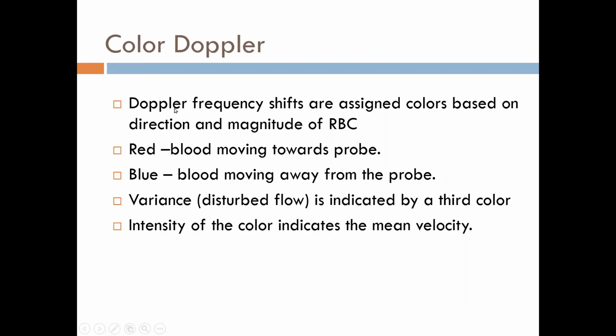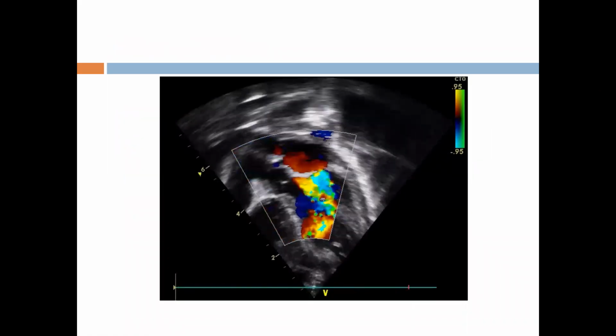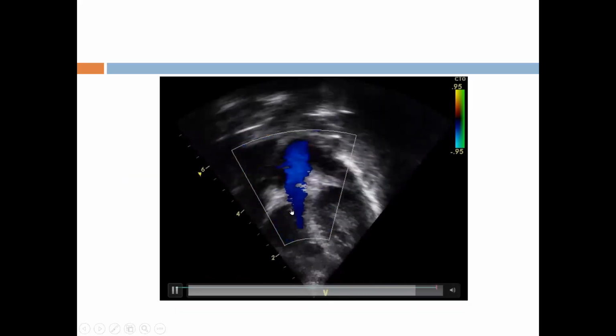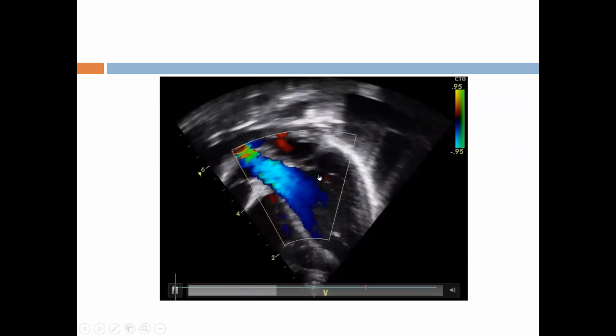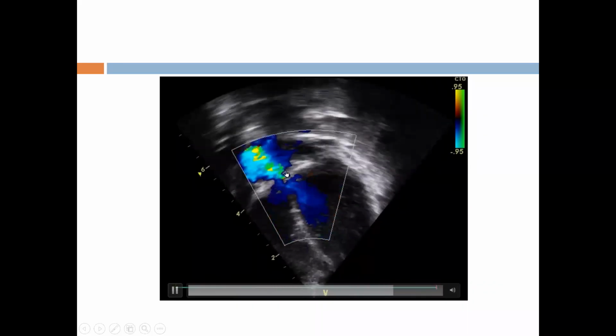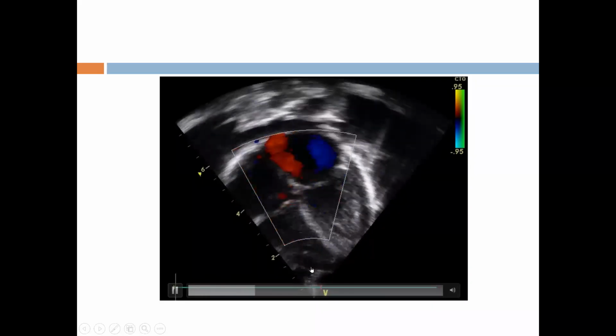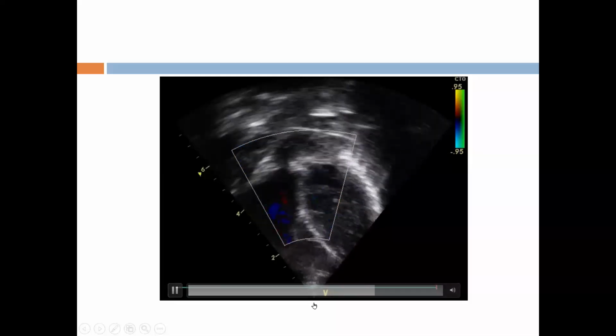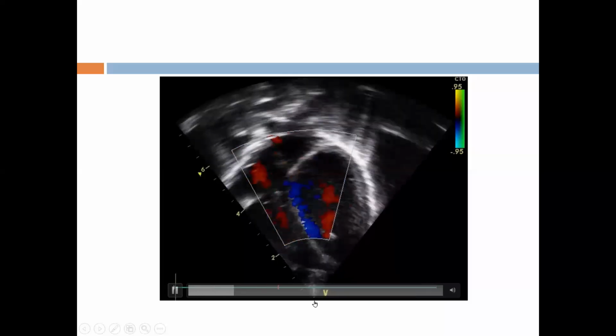So what is color Doppler? Color Doppler basically assigns color to the RBCs based on the shifts. If the RBCs are moving towards the probe, it will give red color. If the RBCs are moving away from the probe, it will give blue color. And if there is a disturbed flow, it will give a third color, which could be green or yellow. The intensity of the color indicates the velocity. So what we can see over here is the red blood, which is moving towards the probe, and now the blue blood, which is moving away from the probe. Red blood does not mean oxygenated, and blue blood does not mean deoxygenated blood. Red means the blood which is moving towards the probe. The probe will be at the apex of the sector at this point.